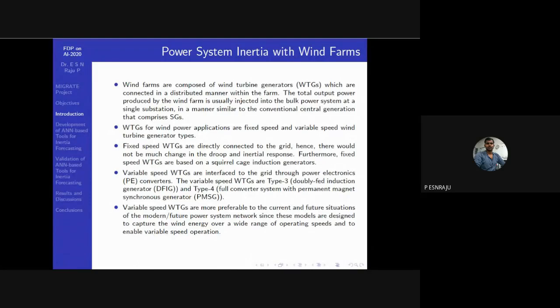If you see the wind turbine generators, we have many types, but mostly people will say there are two classifications. One is fixed speed, another one is variable speed. Coming to the fixed speed wind turbine generators, these are usually directly connected to the grid. Hence, these also will contribute energy to the system. So there would not be much change in the droop and inertial response. And in the fixed speed wind turbine generators, we usually use squirrel cage induction generators.